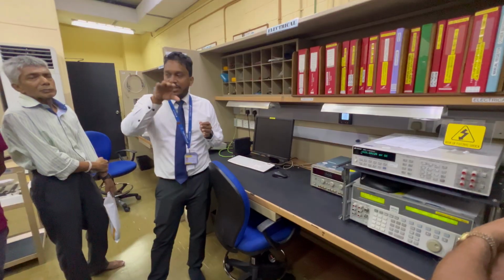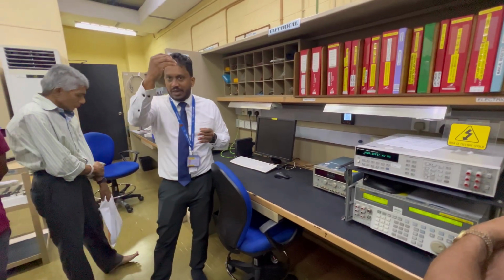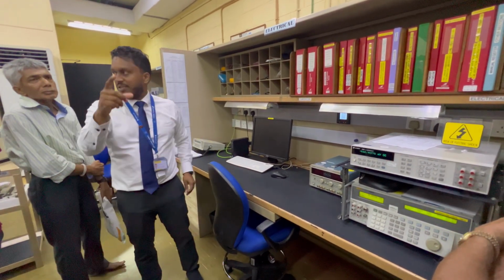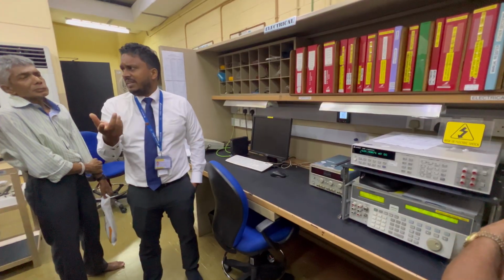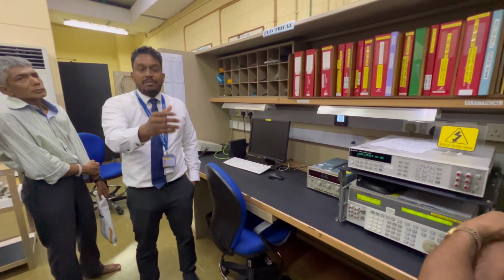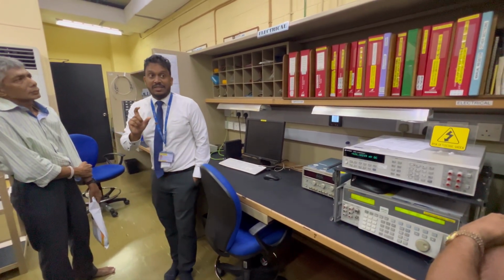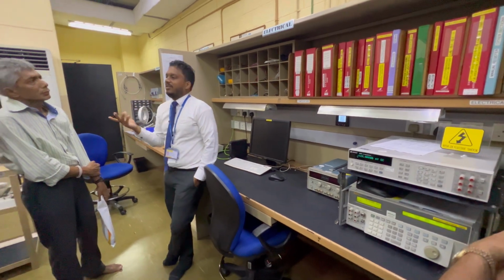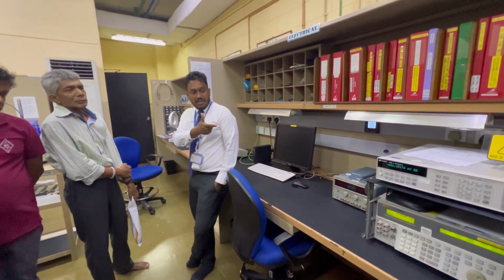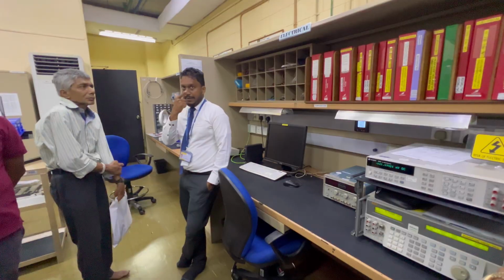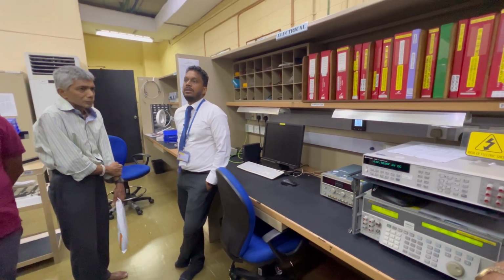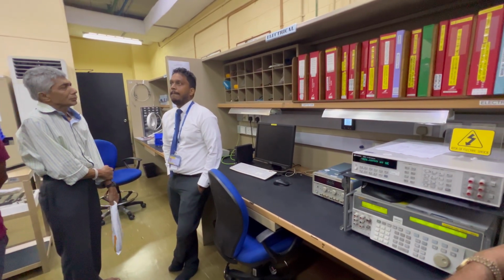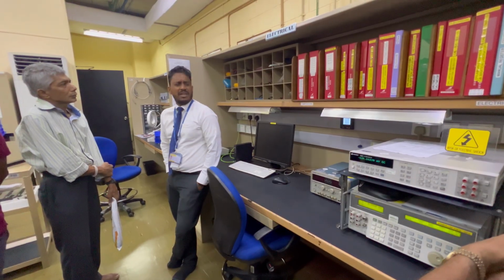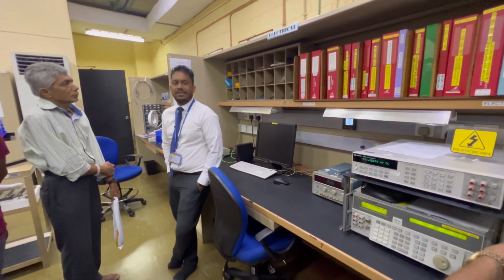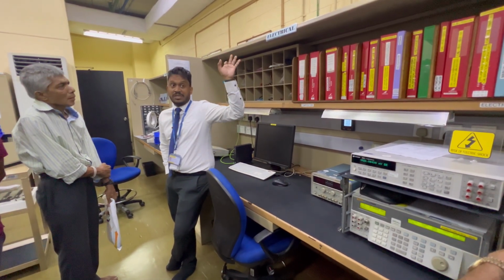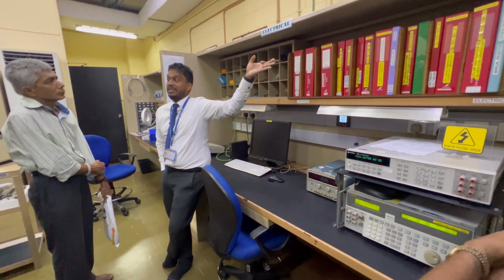Then you take a few parameters and see the deviation. If you see they are not deviating that much, you can actually extend, but only by providing those results. You can't just think, no, this is too costly, this is unique. Each calibration costs around $8,000, and whenever it has to go to Everett, US, it's on the other side of the United States.